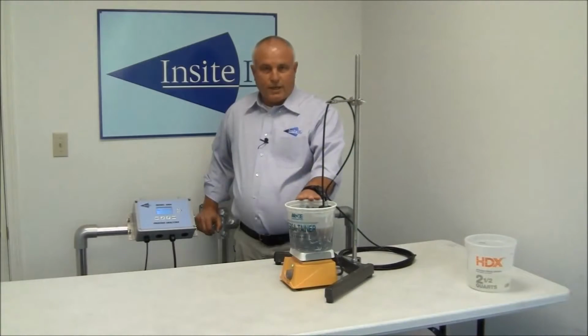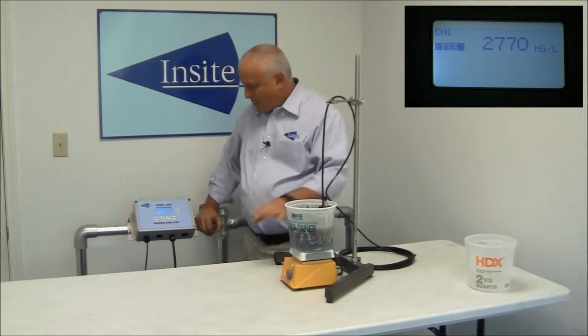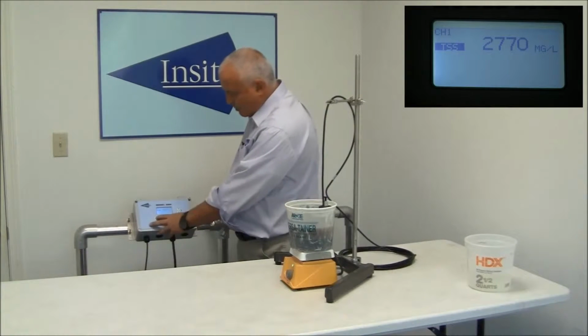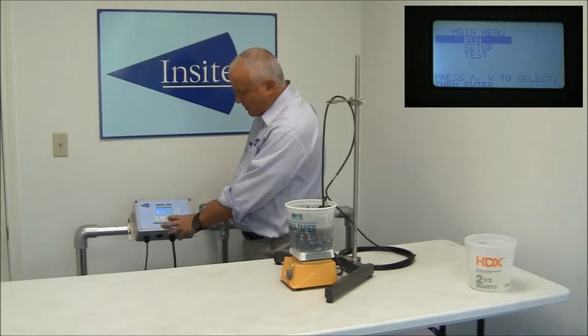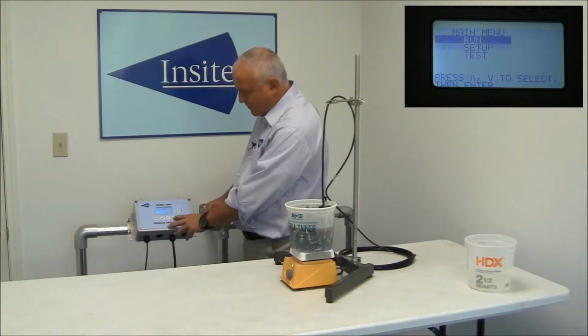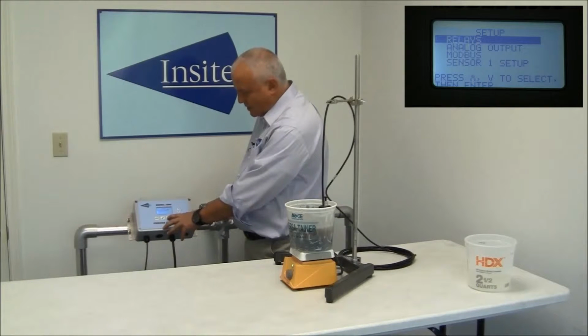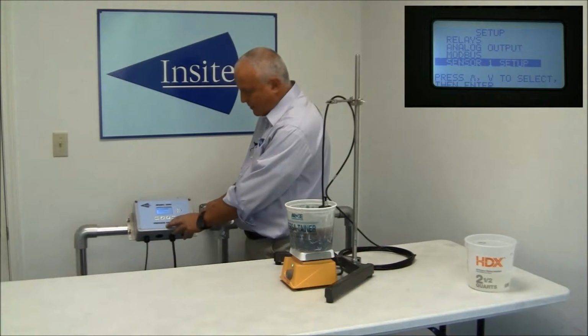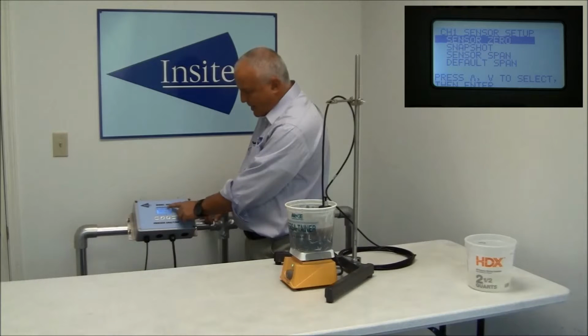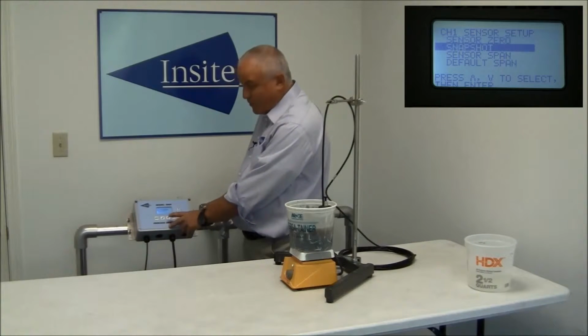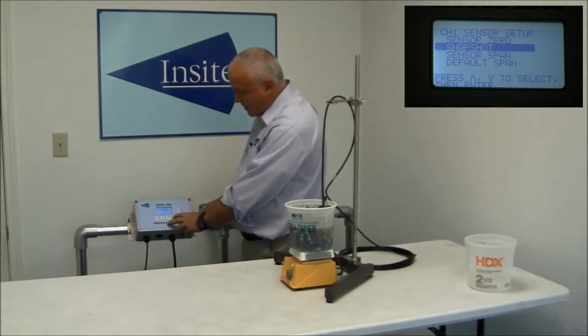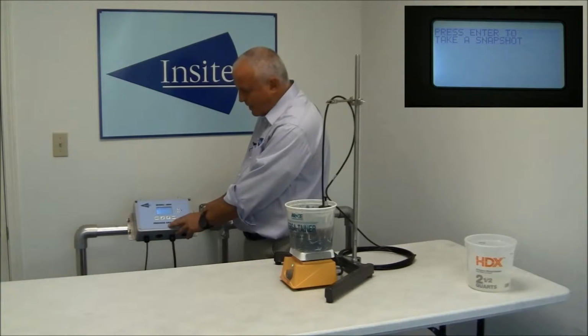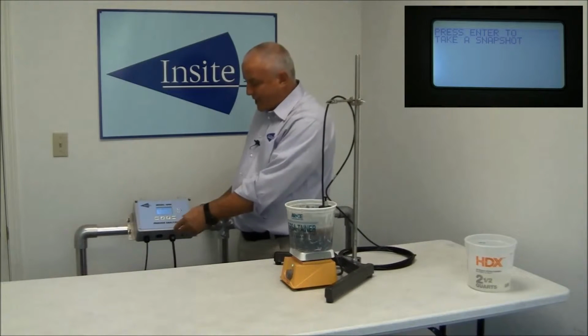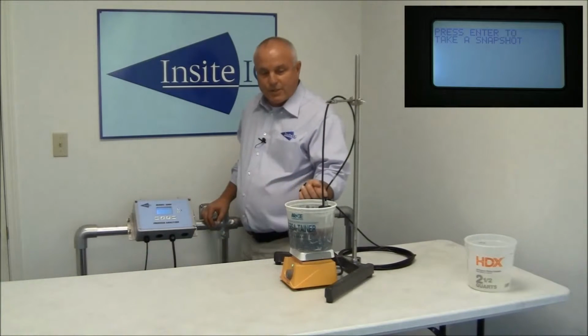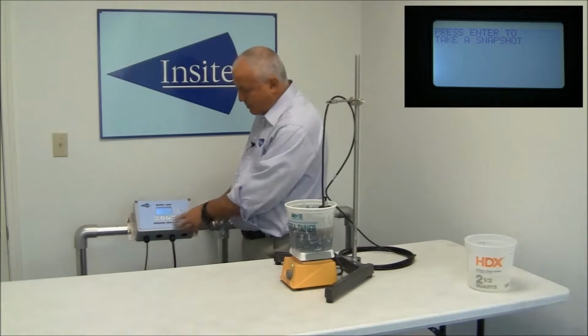So with the sensor in the process, you would simply come to the analyzer, press the menu button, come down to setup, press enter, come down to sensor 1 setup, press enter, and then you'll come down to snapshot, which is the first step of a span calibration, and press enter. Then it's going to ask you, press enter to take a snapshot. It's basically just saying, are you sure you're ready to take a snapshot? With the sensor in the process, you would say yes, press enter.